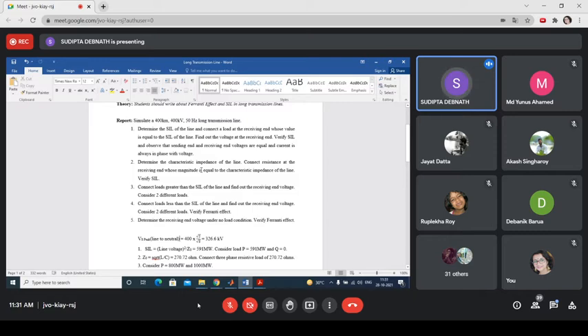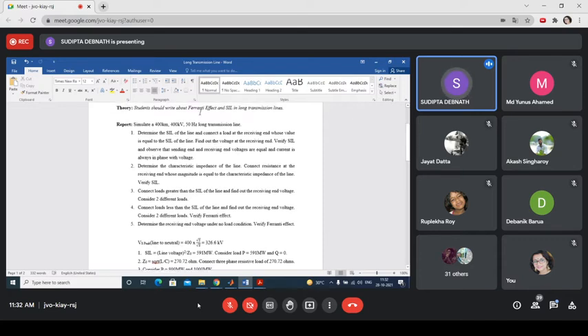Now let us consider: we have examined SIL and seen that the receiving end voltage is the same as the sending end voltage. Our next objective is to observe the Ferranti effect. The Ferranti effect is observed when the receiving end is unloaded, that is kept open, or when the receiving end is very lightly loaded, meaning the load is very small, or less than SIL.